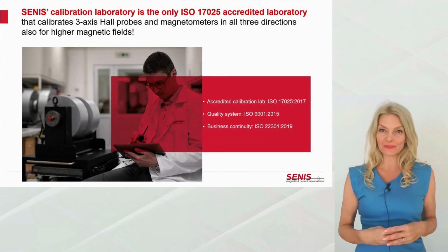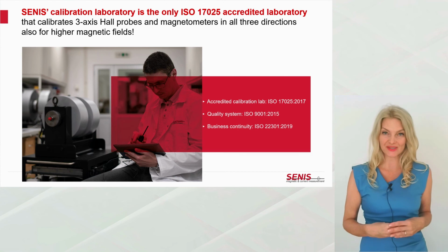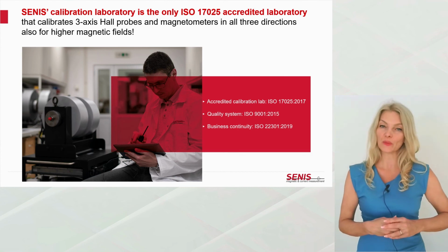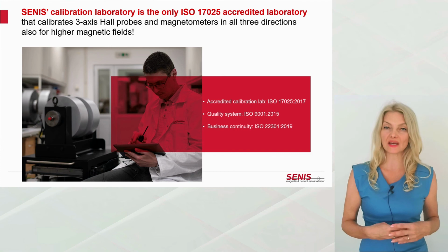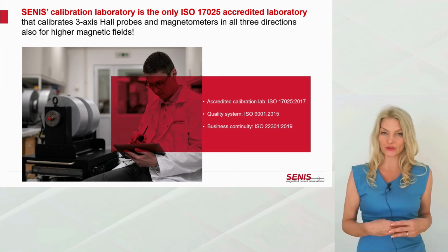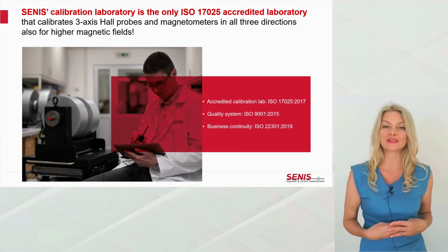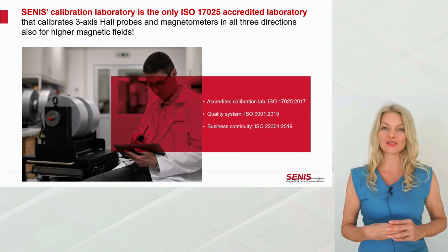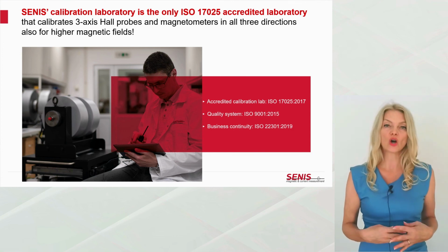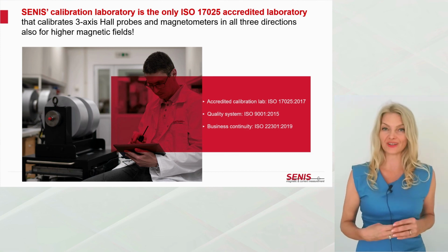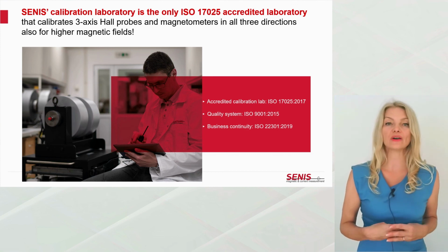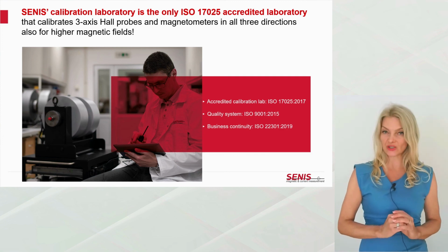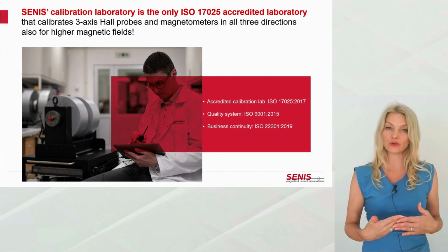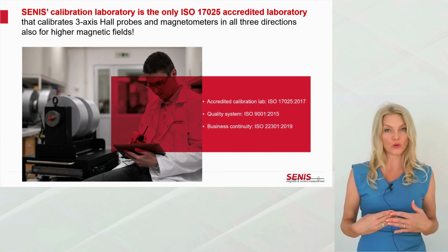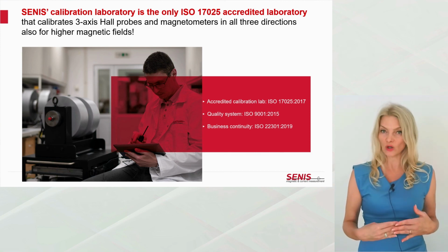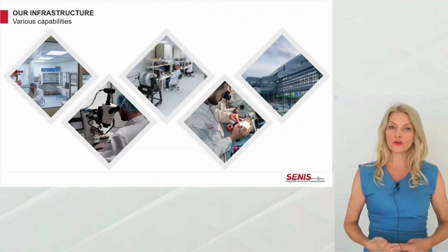We know how to calibrate 3-axis Hall sensors. SENIS Calibration Laboratory is the only ISO 17025 accredited laboratory that calibrates 3-axis Hall probes and magnetometers in all three directions, also for higher magnetic fields. We also have a patented solution for calibration which enables very precise determination of the orthogonality of the 3D Hall sensors. This is our infrastructure.